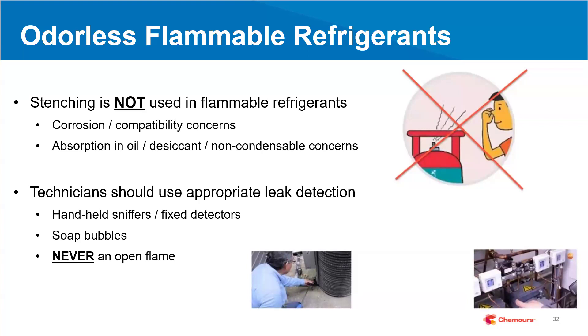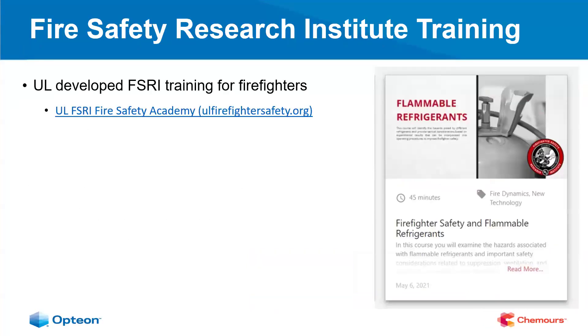Soap bubbles — a tried-and-true method — can still be used with A2Ls because they work off of pressure just like with A1 refrigerants. However, you should never use an open flame for leak detection with any refrigerant. It was never a good idea with an A1 refrigerant, and it's especially not a good idea with a flammable refrigerant.